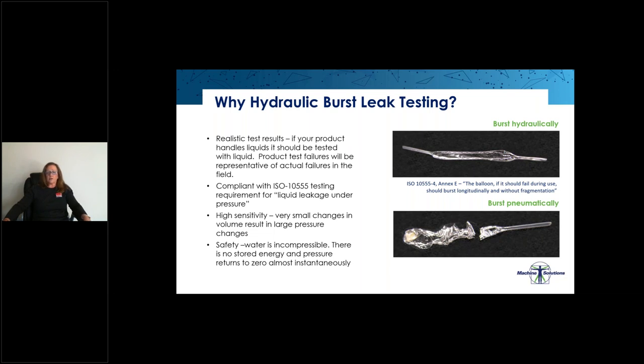I've included some images here of two balloons that are exactly the same but tested differently. The top balloon was tested hydraulically with our HBLT. The balloon below was tested pneumatically with an indeflator. I think the photos speak for themselves. However, both products had a similar burst pressure, but you can see that the failure mode is very different.